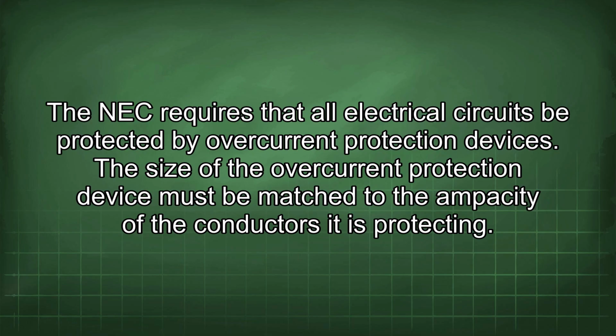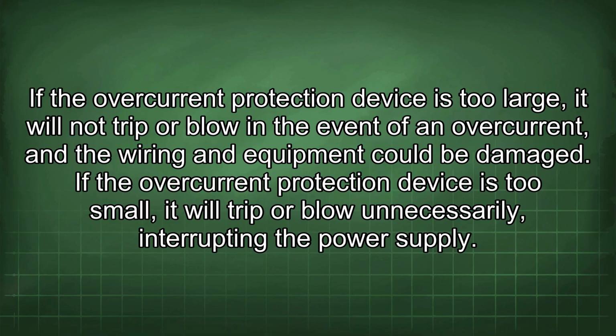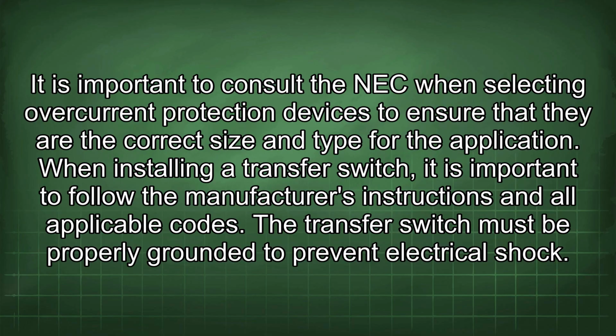The NEC requires that all electrical circuits be protected by overcurrent protection devices. The size of the overcurrent protection device must be matched to the ampacity of the conductors it is protecting. If the overcurrent protection device is too large, it will not trip or blow in the event of an overcurrent, and the wiring and equipment could be damaged. If the overcurrent protection device is too small, it will trip or blow unnecessarily, interrupting the power supply. It is important to consult the NEC when selecting overcurrent protection devices to ensure that they are the correct size and type for the application.